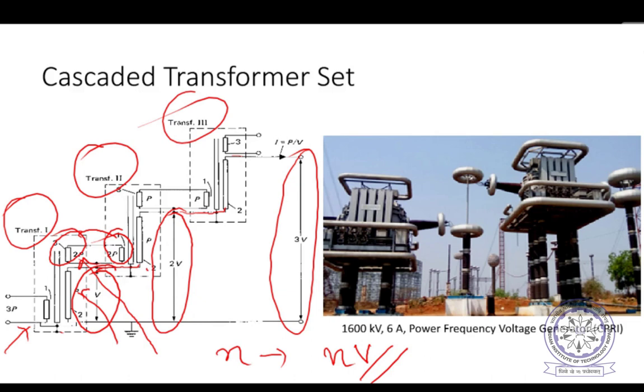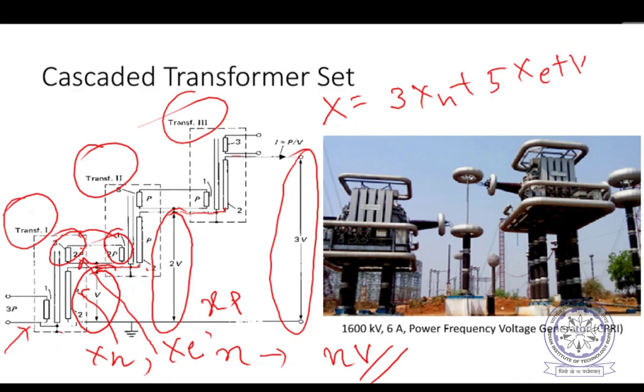What will happen is the reactance. When you are cascading like this, the primary reactance will appear in the secondary, and the reactance will appear in the other transformer secondary, like that. So the effective reactance, for example for 3 stages, is not simply 3XH plus 3XE plus 3XP. Here XH means the high voltage winding reactance, XE the excitation winding reactance, and XP the primary winding reactance. The reactance seen at the secondary side, the output side, is in fact 3 times XH plus 5 times XE plus 14 times XP. So this is how the reactance gets magnified like anything.